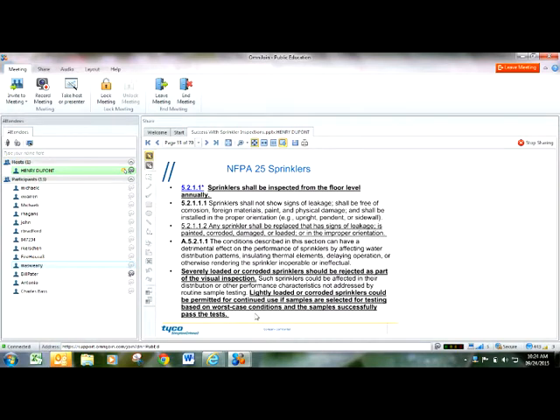We'll talk a little bit about those tests coming up here, but when you are on your inspections, you should be inspecting sprinkler heads from the floor level, and you should be looking for sprinkler heads that have signs of leakage, that are painted, corroded, damaged, or loaded with dust and contaminants. And those heads should be written up to be replaced.